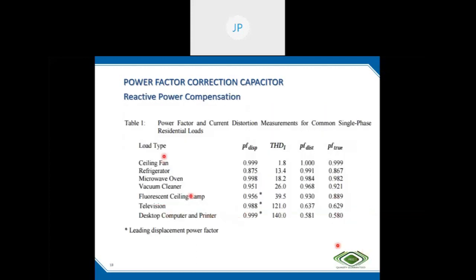And you can see some residential loads having different characteristics. Almost all loads are near unity, but the THD of different loads is increasing. Simultaneously, the distortion power factor is also reducing, and the net power factor is further reducing. If you see all these, for the desktop computer, we have nearly unity, but its THD is 140%. So its distortion power factor is 0.58. The true power factor is the product of these two, and you will get 0.58 only. You can calculate this with our formula: reciprocal of the root of THD squared, 1.4 squared, plus 1. You will get these values.